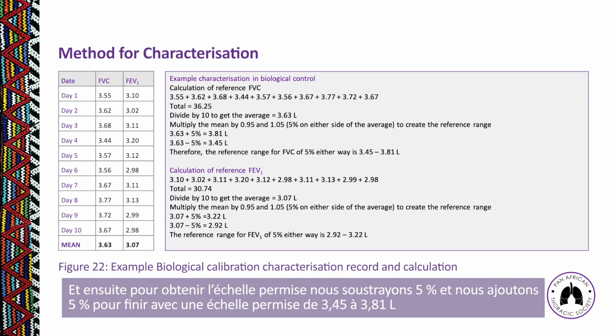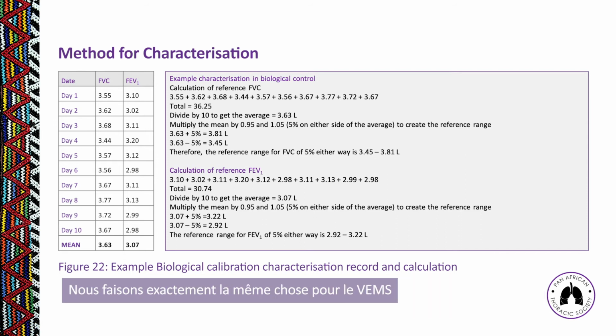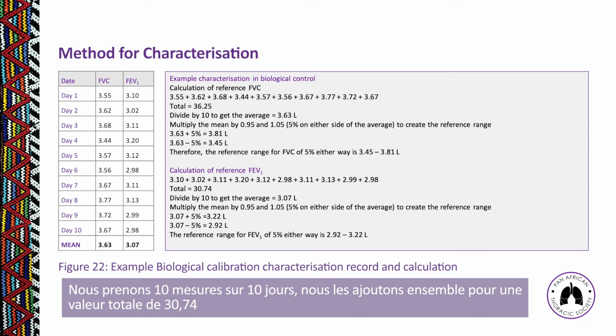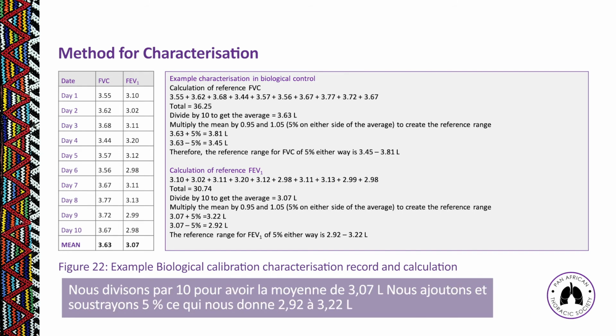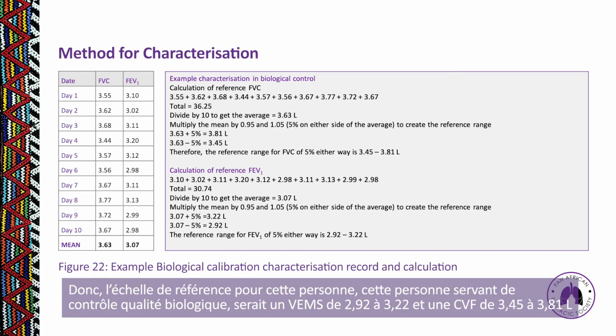And then to get a range allowed, we subtract 5%, we add 5%. And when we do this, we know that the FVC range allowed for this biological control is 3.45 to 3.81 liters. We do exactly the same thing with the FEV1. We take 10 measurements over 10 days, we add them together, we get a total value of 30.74. We divide by 10 to get an average of 3.07. We add and subtract 5% to give us 2.92 to 3.22 liters. So the reference range for this biological quality control person would be an FEV1 of 2.92 to 3.22 and an FVC of 3.45 to 3.81.